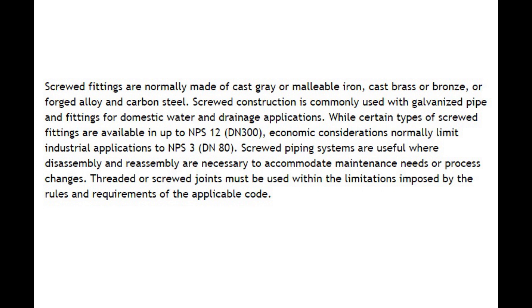While certain types of screwed fittings are available in up to NPS 12 (DN300), economic considerations normally limit industrial applications to NPS 3 (DN80). Screwed piping systems are useful where disassembly and reassembly are necessary to accommodate maintenance needs or process changes. Threaded or screwed joints must be used within the limitations imposed by the rules and requirements of the applicable code.